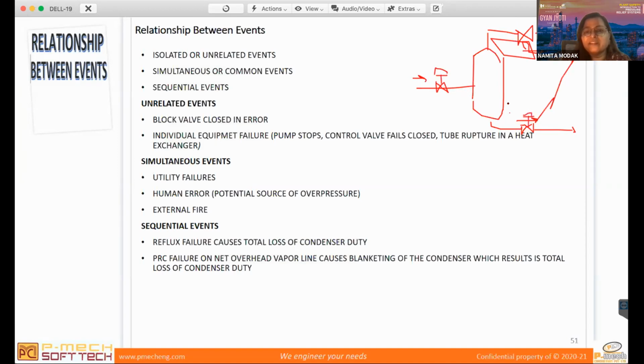So what happened? Your level keeps on increasing. When it reaches high liquid level, what happens? Your compressor trips, because you will not allow vapor to enter your compressor. It will damage the compressor. So ultimately it will become vapor blocked in also. In this scenario, it's a sequential event. You have a liquid blocked in, and after some time, you will have a vapor blocked in also.